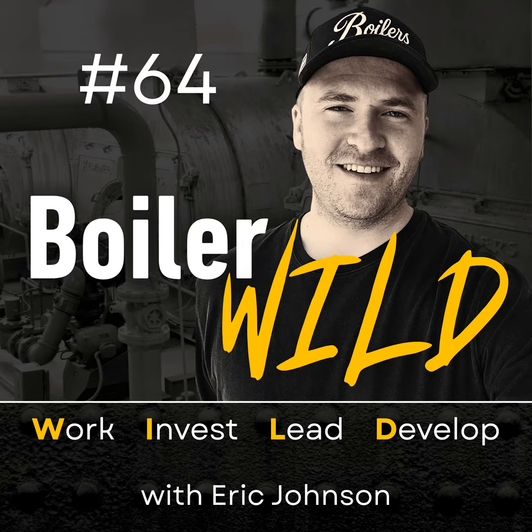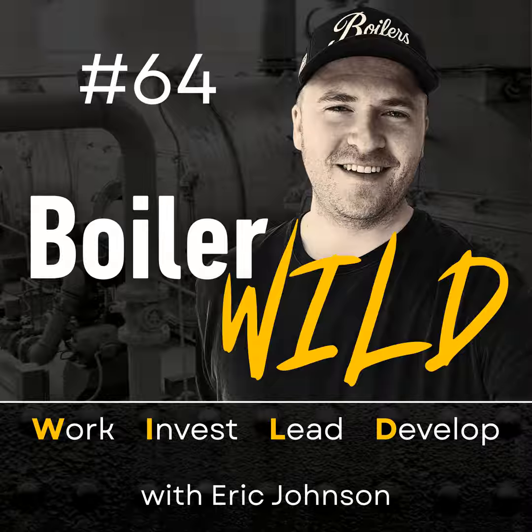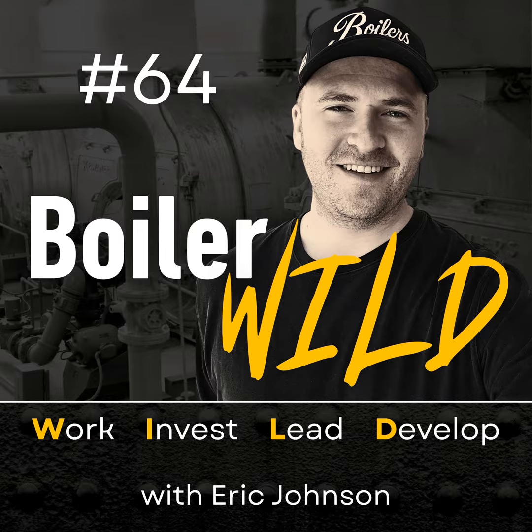Typically though, if you still got good feeling in your hand and maybe some good hearing, if the boiler room is decently quiet, you can hear when a switch resets or feel when a switch resets. But I have watched boiler operators think that in order to restart the boiler, they have to go around and push all the resets. Or even service technicians, they go around and push all the resets before they start a boiler. And that can mask problems when you are pushing all the resets before you start a boiler.